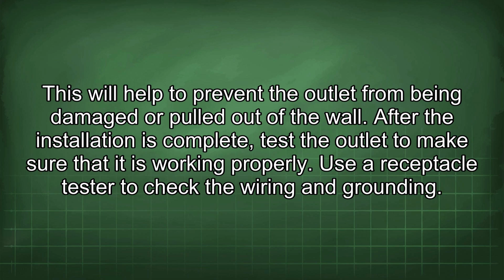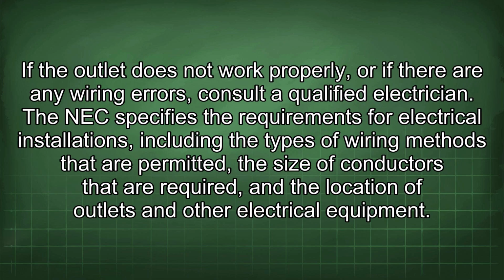After the installation is complete, test the outlet to make sure that it is working properly. Use a receptacle tester to check the wiring and grounding. If the outlet does not work properly, or if there are any wiring errors, consult a qualified electrician.